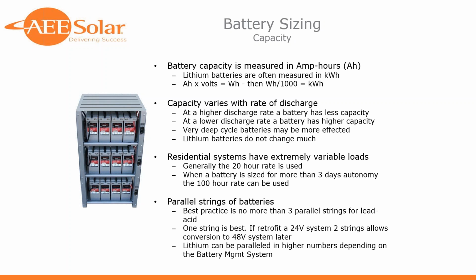And residential systems, for self-supply, you're looking at a daily rate generally, so 20 hours. Although if most of the loads are concentrated within 8 hours, you may be wanting to use the 8-hour rate for those.